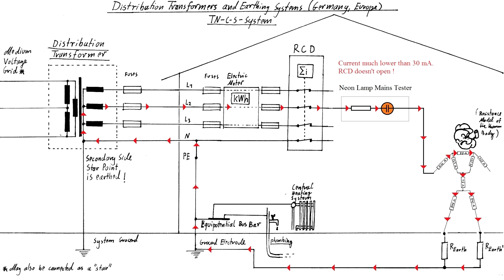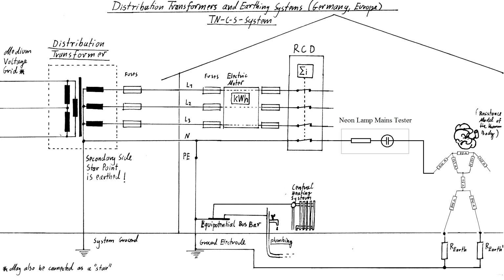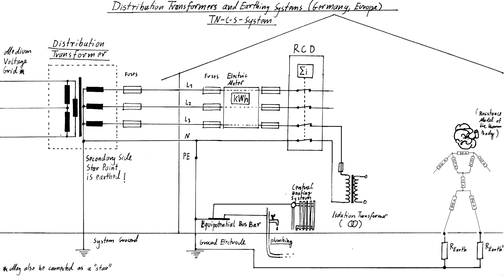If you apply the tester to the neutral on the other hand, both sides of the tester are basically connected to earth ground, which means that there should ideally be no potential difference between its two electrodes. Therefore, no noteworthy current flows through the lamp and it doesn't light up at all. If now an isolation transformer is connected between one phase and neutral and the neon tester is applied to either one of the ends of its secondary winding, no current is flowing because no closed electric circuit exists.